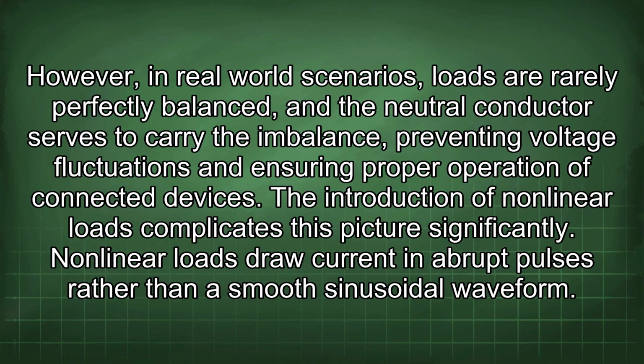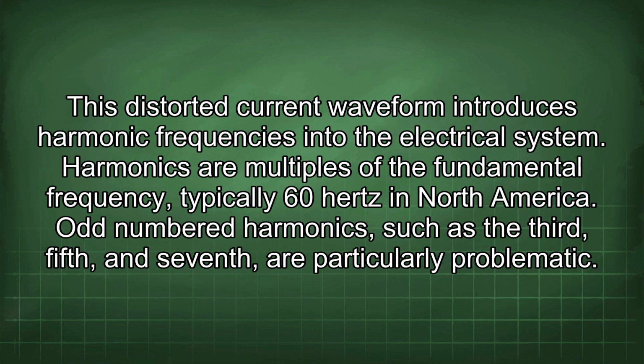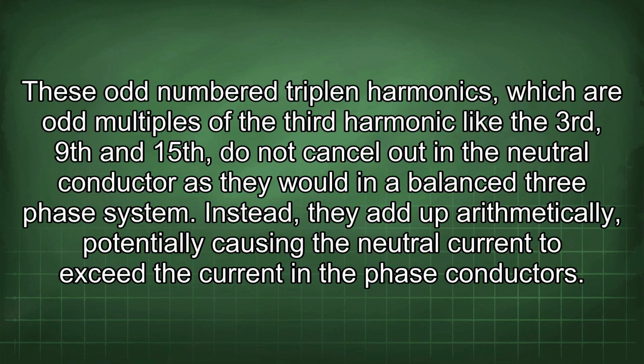Nonlinear loads draw current in abrupt pulses rather than a smooth sinusoidal waveform. This distorted current waveform introduces harmonic frequencies into the electrical system. Harmonics are multiples of the fundamental frequency, typically 60 Hz in North America. Odd-numbered harmonics, such as the 3rd, 5th, and 7th, are particularly problematic. These triplen harmonics, which are odd multiples of the 3rd harmonic like the 3rd, 9th, and 15th, do not cancel out in the neutral conductor as they would in a balanced three-phase system. Instead, they add up arithmetically, potentially causing the neutral current to exceed the current in the phase conductors.